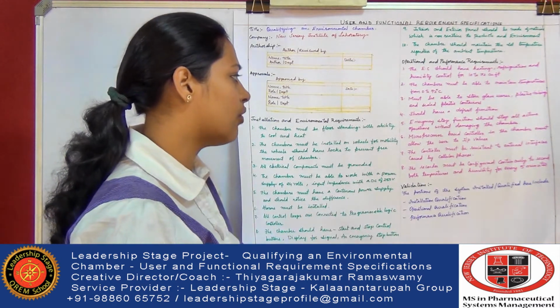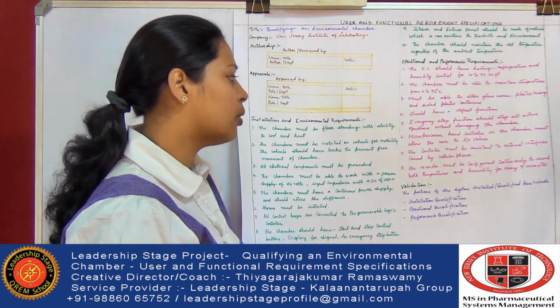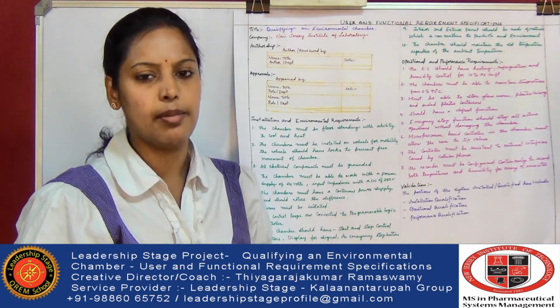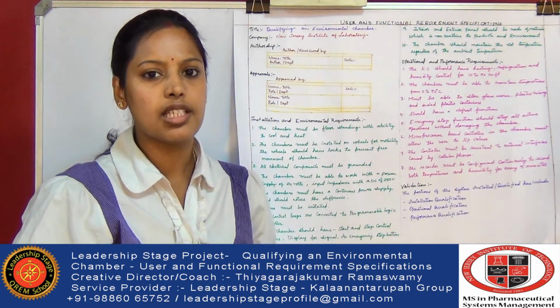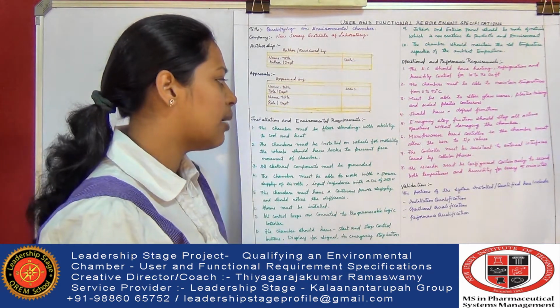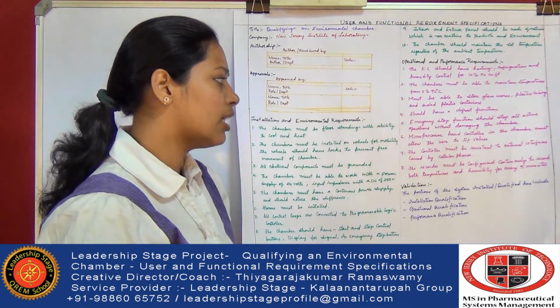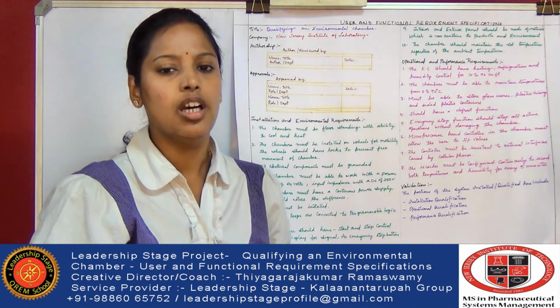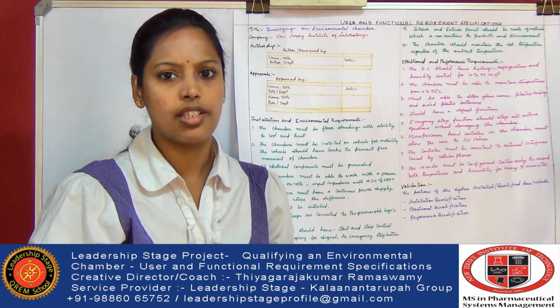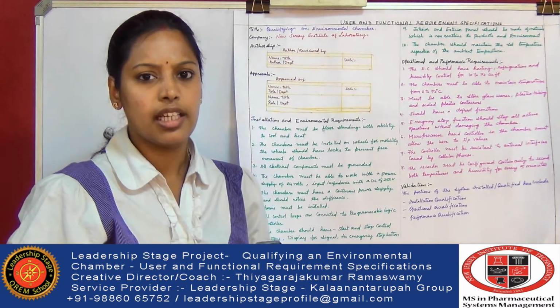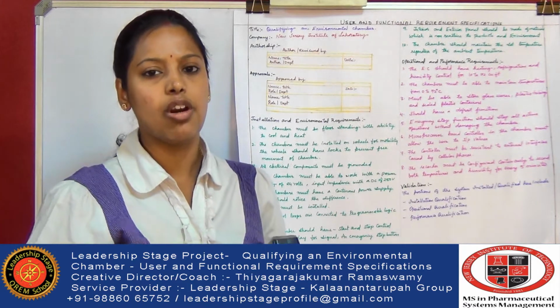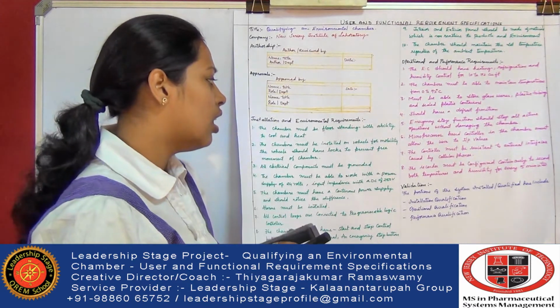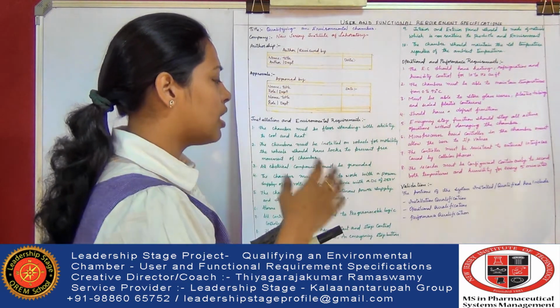The recorder must be configured to continuously record both temperature and humidity every 5 minutes. This is one of the requirements. This is because it is a biological laboratory, and temperature recording is very important, and any variation in the temperature may lead to a fatal condition for the cells. So temperature maintenance is very important, and it has to be recorded every 5 minutes. These are the operational requirements.